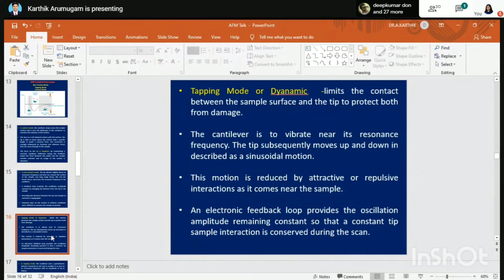When using that concept, the tapping mode measures the entire surface area, right? Whenever you measure the surface of a sample, it cannot always be uniform. There is a depth variation, a depth and height profile. Depending upon the depth and the height, the height of the tip is adjusted by the cantilever, right? So anyway, we have to maintain the feedback loop in order to hold the particular height.